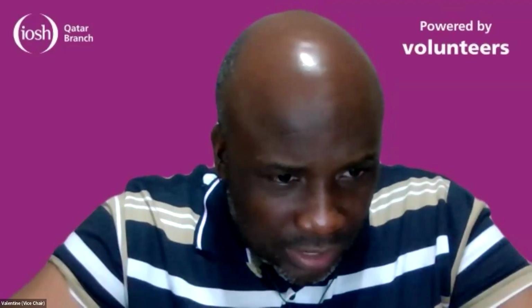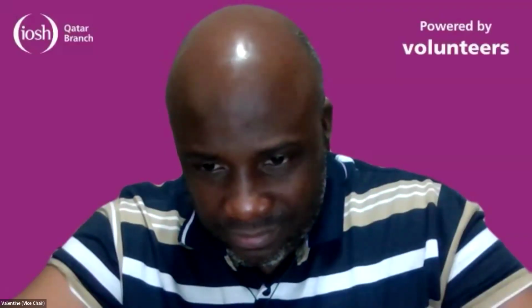Thank you. Another question is, suppose a person is inside the room when the FM200 is released, is the gas harmful to that person? Yeah, I just shared in the presentation also. This has 9% of oxygen content. For example, I'm sitting in this room. If the fire occurs, the gas is discharged. I will not starve for oxygen. I will have the time to move out of the room without any issues. So you can go out of the room, nothing will happen, since there is oxygen content. But you are not supposed to inhale the particular agent continuously. You understand? So nothing will happen. At the same time, you are not supposed to inhale continuously. You have to just evacuate yourself from the area where the fire is happening.